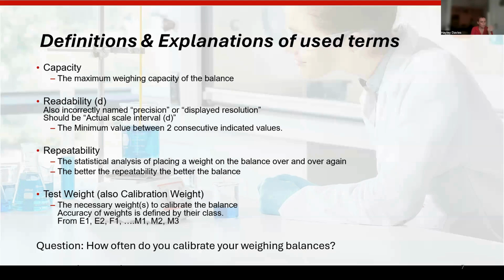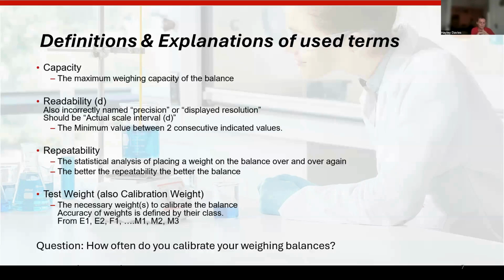Okay, so what we'll do is we'll go over a few more questions, and then we've got a little video at the end of how to calibrate the balance. If we've got time, we can play that. But calibrating your balance should be done as soon as you have unpacked it, as soon as it's arrived, and when you've placed it in situ. If it's a laboratory balance, it really does depend on how often you are using the balance. Some SOPs are written in that you need to have calibration once a year.